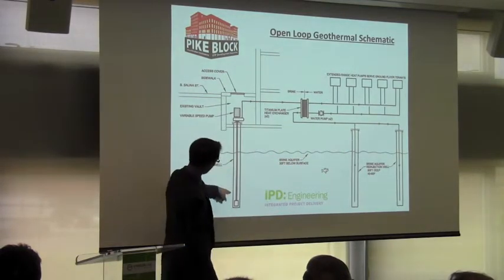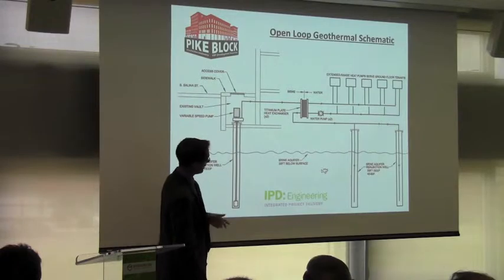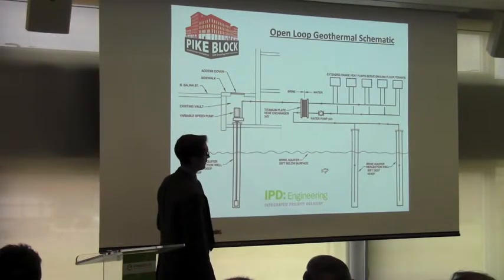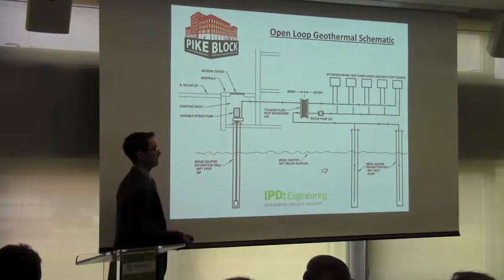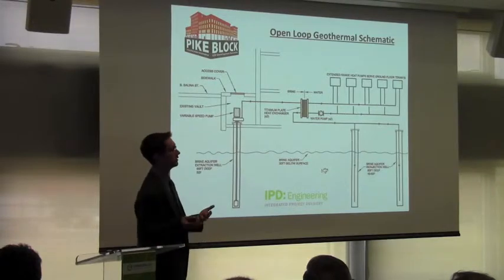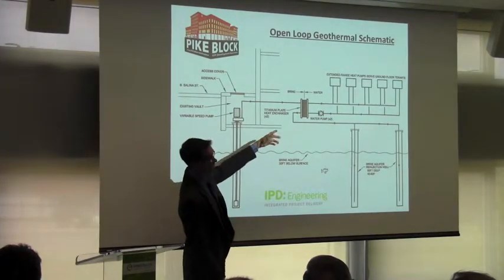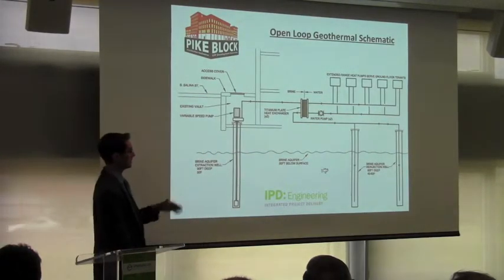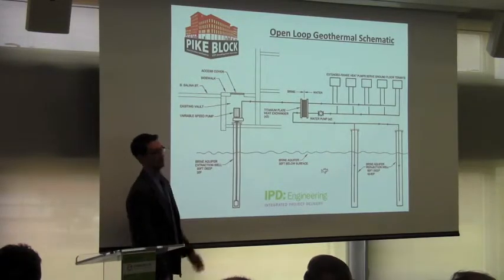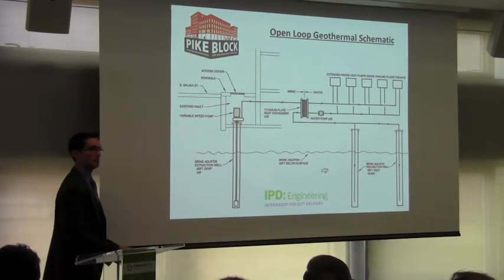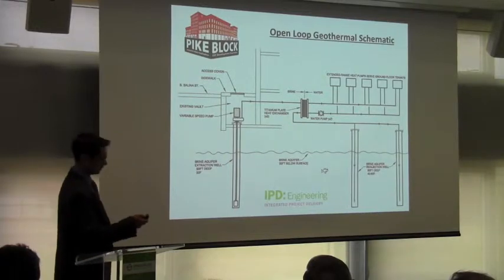So I talked about there being a variable speed drive on this pump. The idea there is I don't want to be pumping as much brine as I can be. I want to pump as little as I can to meet the load. So as the load in the building from the heat pumps rises and falls, I'm varying the speed of my pump to meet the needs of the building.